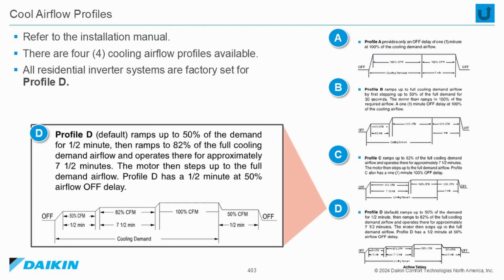Profile D ramps up to 50% of the demand for 1/2 of a minute, then ramps up to 82% of the full cooling demand and operates there for approximately 7.5 minutes. The motor then steps up to the full demand airflow. Profile D has a 1/2 minute at 50% airflow off delay.